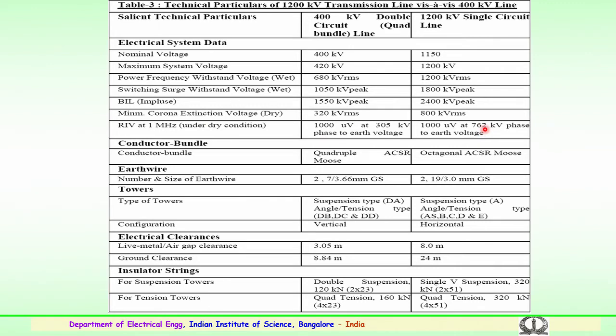The RIV (radio interference voltage) measured at 1 MHz under dry conditions must not exceed 1000 microvolts at 305 kV phase-to-earth voltage for 400 kV, and the same 1000 microvolts at 762 kV for 1200 kV. How good the hardware is — the conductors, hardware, corona control rings, and proper design — plays a key role, as the radio noise and audible noise must be maintained at the same level even as voltage levels increase. Conductor bundles: for 400 kV, 4-conductor quadruple ACSR moose is used; for 1200 kV, octagonal 8-conductor ACSR bundles are used.